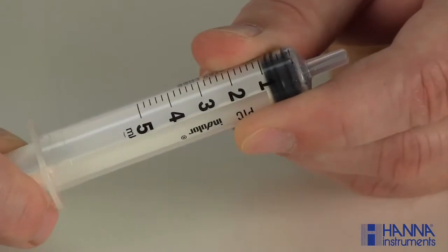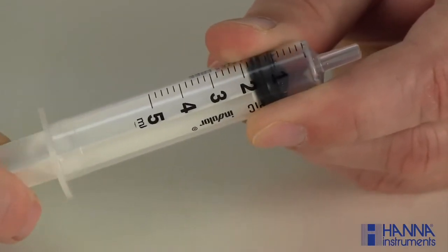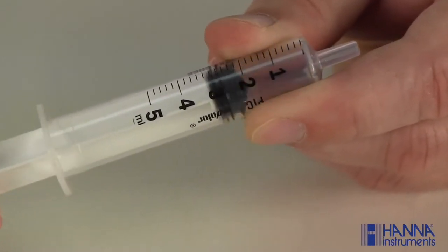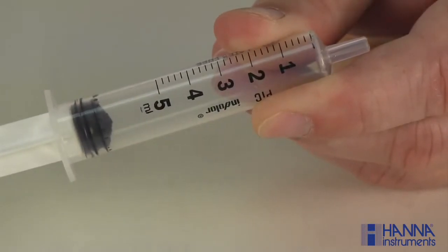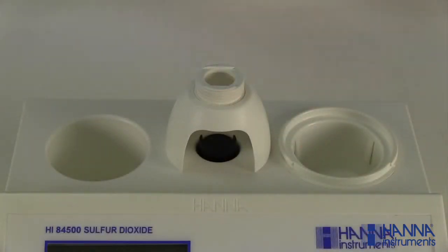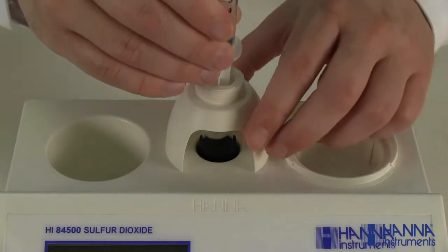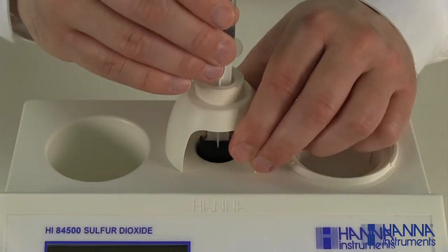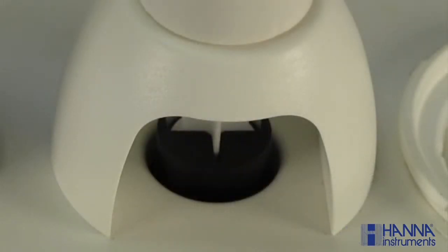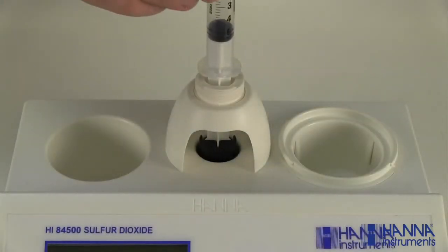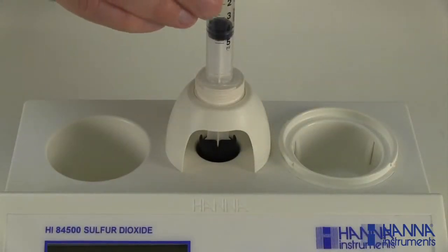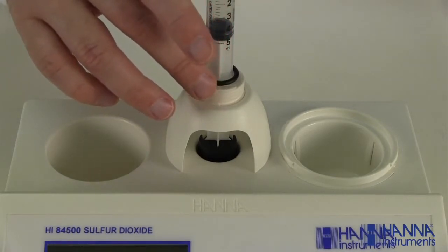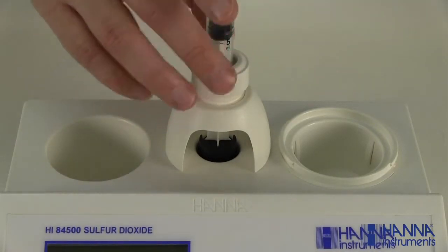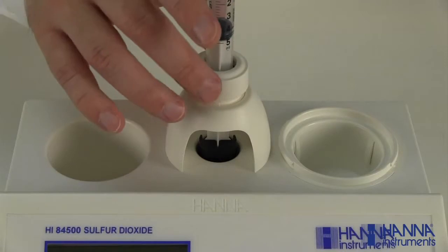To install the dosing pump, extend the plunger on the 5 milliliter syringe to its maximum volume. Place the syringe in its dedicated spot on top of the titrator. Be sure to arrange the bottom of the syringe into the holder on the pump and lock it into place. Once in place, lower the barrel until it sits flush on the holder. Put the O-ring and fixing nut over the syringe and turn clockwise to secure in place.